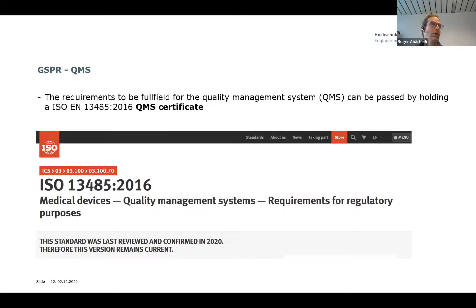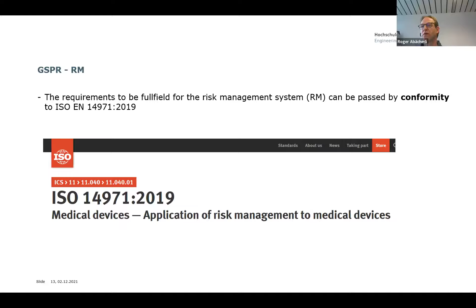So next point. Once we know that, we will see that in this Annex 1, there is a requirement for a quality management system. That can be fulfilled by having a quality management system which is certified. So you go to a notified body through a certification process through that standard here. And if you get the certificate as a company, then you are okay. This is not only true for companies, it is true for everybody who has the function of a legal manufacturer. Just to be reminded, you can become a legal manufacturer very fast with those definitions I just showed. Another point is that you have to have a risk management system. That can be shown by conformity to the standard that I am showing you here. I do not want to go into more detail because we want to focus on AI.